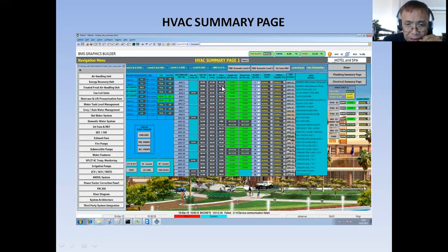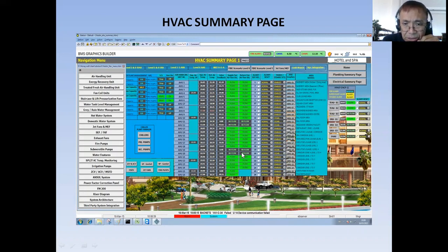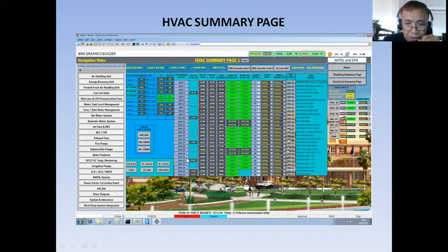If you can see a valve that is closed, you will also see no airflow — no flow. Meaning these air handling units, H11 and H12, maybe they are shut down or under maintenance. So you already have an idea which air handling units are not working. Also H19 and H20 — there is no flow there. So you will always be prompted: I have problems with four air handling units. You can call the maintenance people and ask what's happening with H11, H12, H19, and H20 — whether they are doing preventive maintenance.